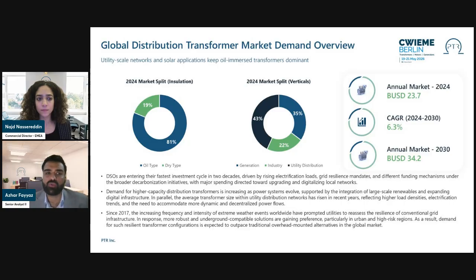If we talk about the insulation split, globally oil-immersed transformers continue to dominate. Most of this demand is coming from utility and solar applications due to cost competitiveness and thermal performance. So if we compare both power and distribution transformers, while the distribution transformer segment does not face the extreme bottleneck similar to power transformers, demand is still there.